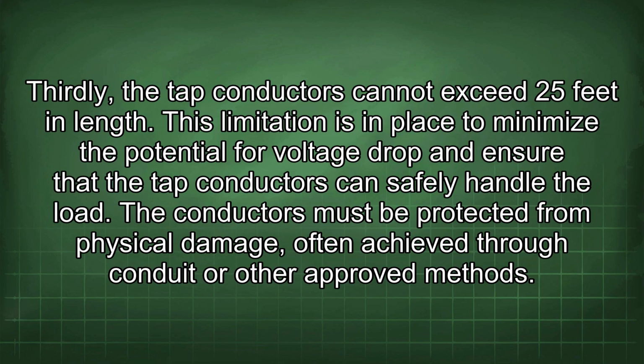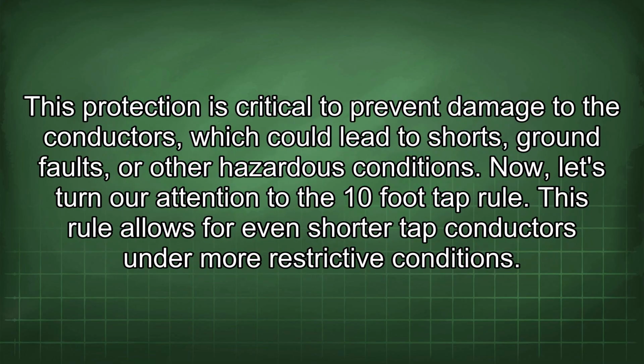Thirdly, the tap conductors cannot exceed 25 feet in length. This limitation is in place to minimize the potential for voltage drop and ensure that the tap conductors can safely handle the load. The conductors must be protected from physical damage, often achieved through conduit or other approved methods. This protection is critical to prevent damage to the conductors, which could lead to shorts, ground faults, or other hazardous conditions. Now let's turn our attention to the 10-foot tap rule.